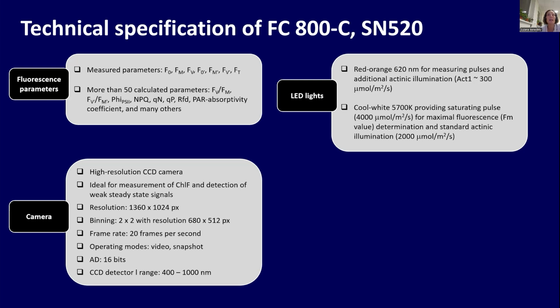5700 kelvins, and these provide strong light, so they are dedicated to the saturating pulse. In your device, the saturating pulse is approximately 4000 micromoles per square meter per second. Exactly, it's 4020. So we always have a calibration of your light. We have calibration files, and you should also have these graphs in your documentation folder. So the saturating light is 4000, and this white light can be used also as actinic light. The saturating pulse is restricted to a short time, not to overheat the LED panels, but the actinic light, which gives in your device more than 2000 micromoles, can be used for seconds, minutes as an actinic light, so very strong light.